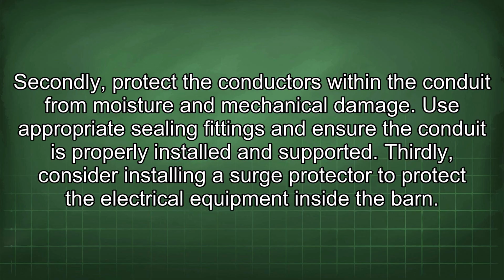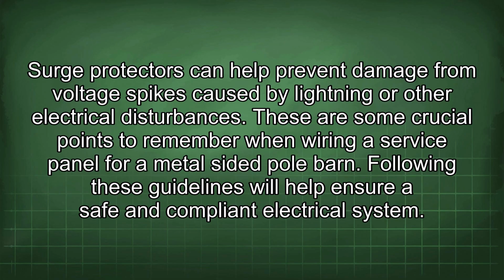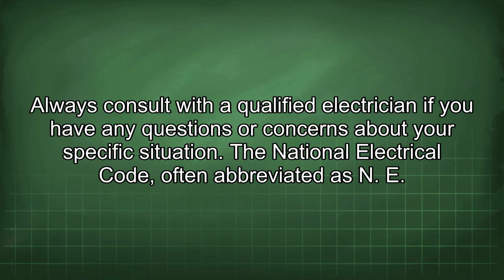Secondly, protect the conductors within the conduit from moisture and mechanical damage. Use appropriate sealing fittings and ensure the conduit is properly installed and supported. Thirdly, consider installing a surge protector to protect the electrical equipment inside the barn. Surge protectors can help prevent damage from voltage spikes caused by lightning or other electrical disturbances. These are some crucial points to remember when wiring a service panel for a metal-sided pole barn. Following these guidelines will help ensure a safe and compliant electrical system. Always consult with a qualified electrician if you have any questions or concerns about your specific situation.